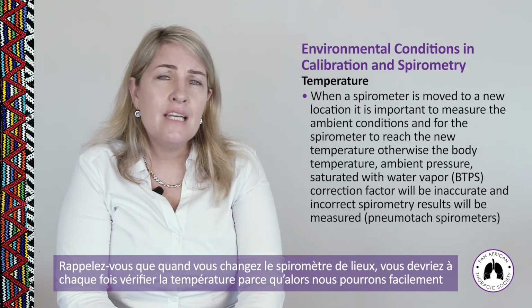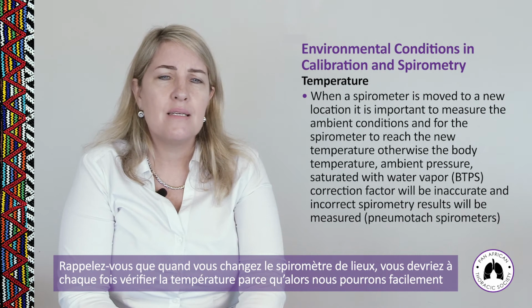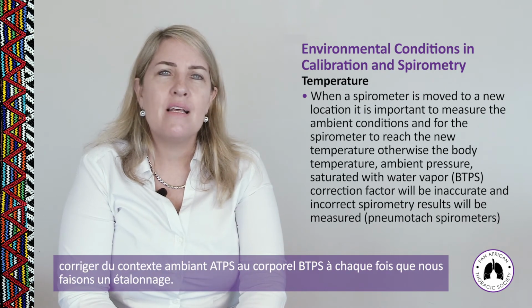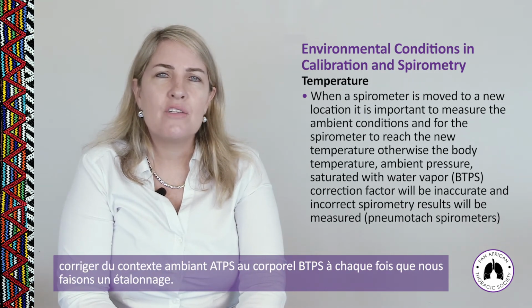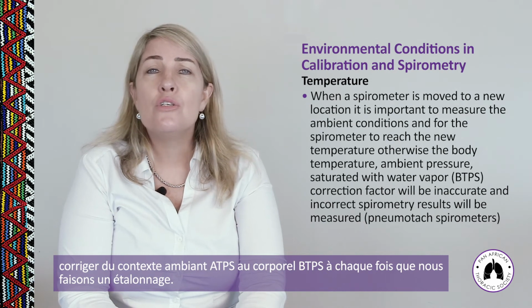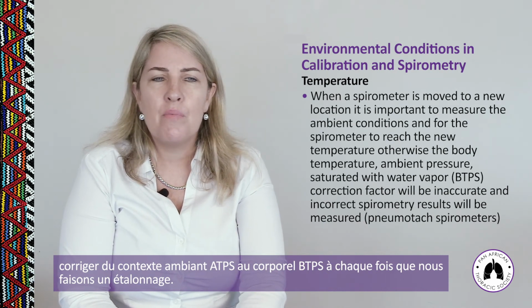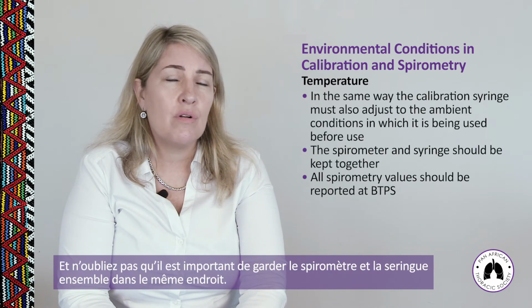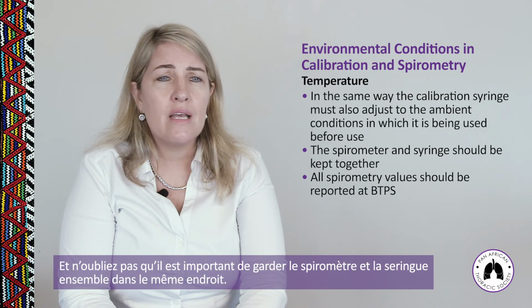Remember that when you move your spirometer to a new location, you should really look at the temperature each and every time you get to a new place. And therefore, we can make the adjustment easily if we make these corrections for ATPS to BTPS every time we do a calibration itself. And remember, it's important to keep the syringe and the spirometer stored together in the same place.